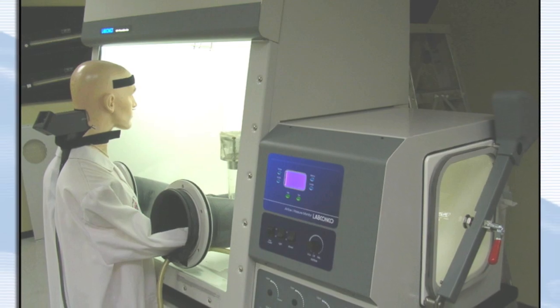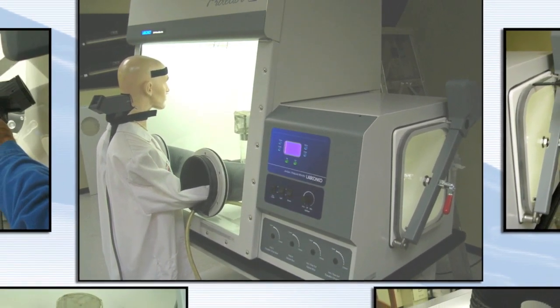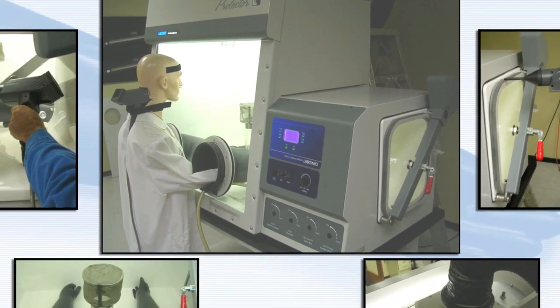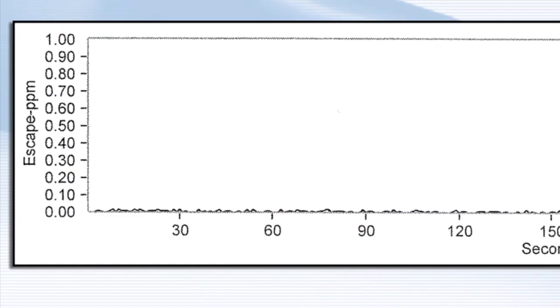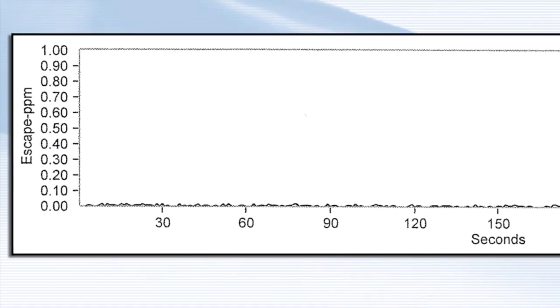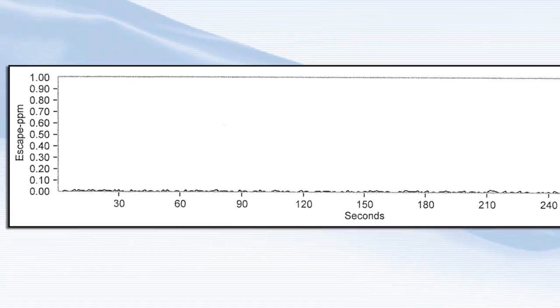These boxes have also been tracer gas tested, indicating fast cleanup times from contaminated conditions. Tests measured less than 0.05 ppm average tracer gas levels during perimeter scan testing after 5-minute dilution times, surpassing ASHRAE 110 standards.